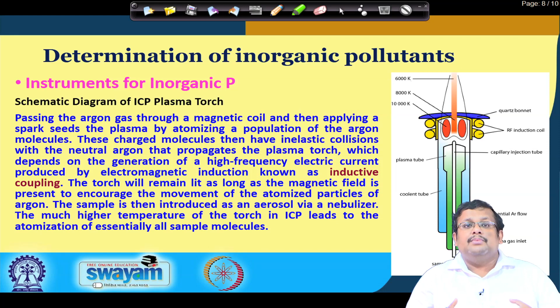The sample is then introduced as an aerosol via a nebulizer. The much higher temperature of the torch in the ICP leads to the atomization of essentially all sample molecules. For complete atomization of all sample molecules, you need a very high temperature that can only be created by the production of plasma. And for creating that plasma, you require inductive coupling, and for that inductive coupling you require these radio frequency coils. So, this is how the plasma torch basically works, and this is the central working principle of this ICP AES.